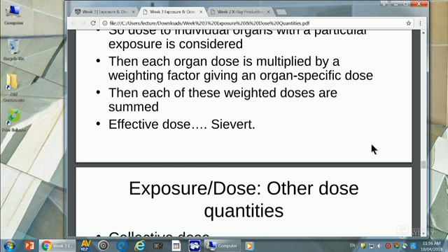And this is why I said right at the beginning, this only measures what's coming out of the X-ray tube. Translating that to what's actually getting to the patient is a tricky science, but if you look at the papers, they show there is a pretty strong correlation between the dose calculations here and the dose calculations here. They do agree pretty well, even though there are weaknesses for the reasons you say.